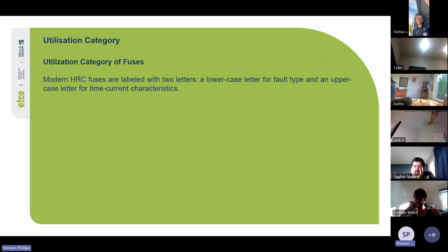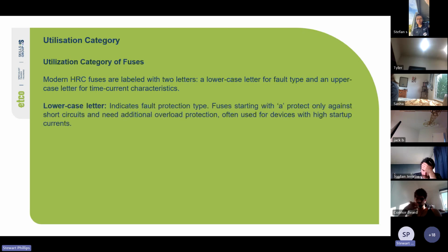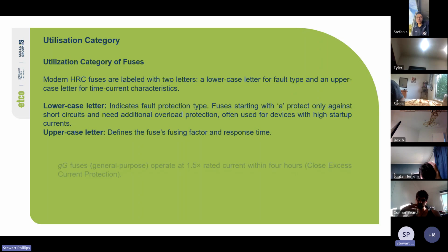Cool. So utilization category of fuses. Modern HRC fuses are labeled with two letters, a lowercase letter for fault type and an uppercase letter for time current characteristics. The lowercase letter indicates fault protection type. Fuses starting with a protect only against short circuits and need additional overload protection, often used for devices with high startup currents like motors. And your uppercase letter defines the fusing factor and response time.